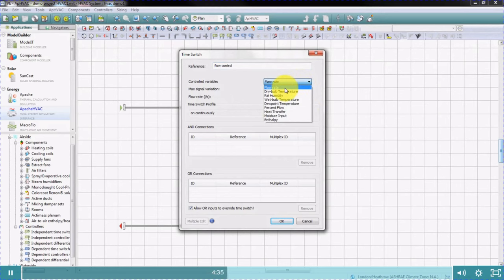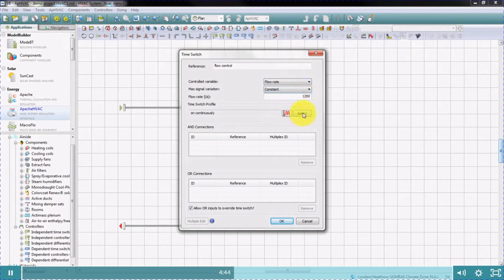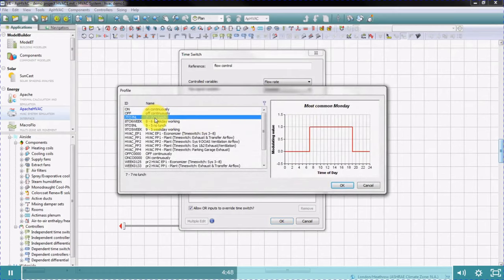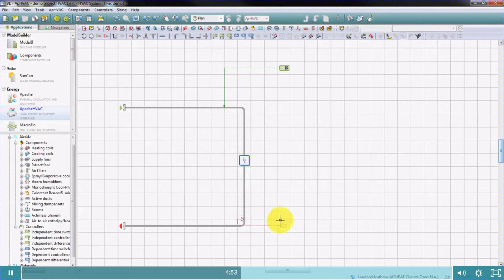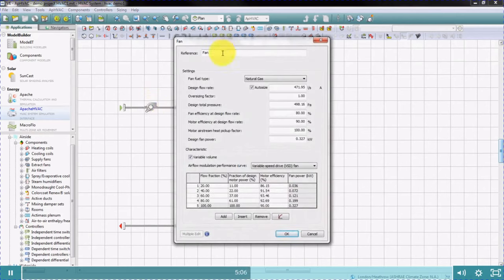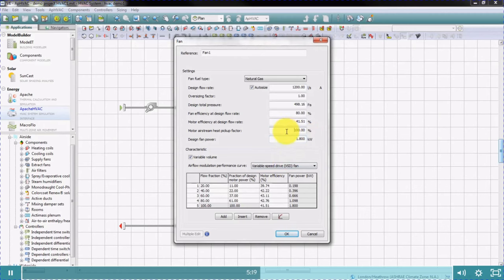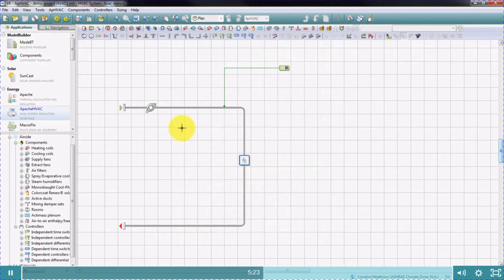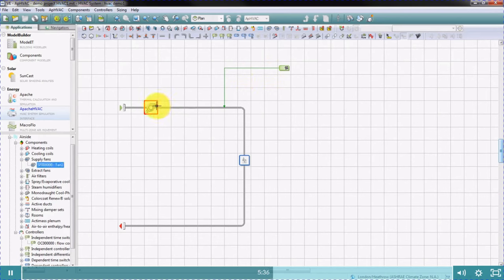We'll select flow rate as the control variable and the maximum flow. We'll control the flow rate using a time switch profile by clicking the select icon, where you can see all the profiles in your projects. If you wish to place a fan in the system, you can use these icons here. Note, the fan symbol does not define the flow in the system — the flow is defined by the control. The fan in the system is used to define the electricity consumption of the fan.